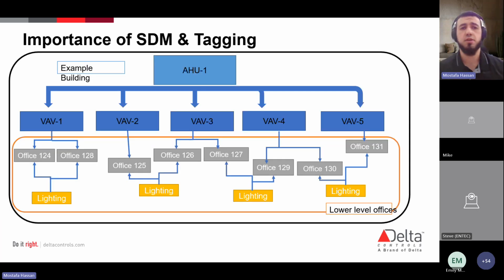So, with the importance of semantic data modeling and tagging, you have here a building with different equipment and sensors. In order to write a proper control logic or sequence of operation, you'll put it into the controller, from which you'll collect data and start generating reports, sending them to your building owner. You need to define relationships between these different parameters, these different objects, like the air handling unit and the VAV. So here we don't really know. We only know that the air handling unit is feeding the VAV and the VAV is feeding those specific spaces.